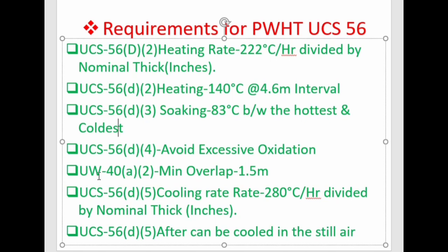The next statement, given in UW-40(a)(2), is that the minimum overlap is 1.5 meters. If the vessel is too large to accommodate in a single PWHT cycle and requires two cycles, the first portion is heat treated and then the second portion is inserted into the furnace. At that time, at least 1.5 meters of the area previously heat treated shall be present in the area to be heat treated.